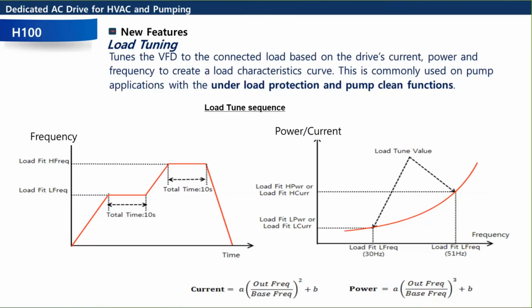So when I say the load, typically this is going to be used on pumps, because if you do a load tune, you're going to be able to do some more advanced features, which we'll mention next, like a pump clean function or under load protection. So like a belt break or broken shaft or pump clean, if something gets jammed up. This diagram on the left is showing the actual load tune. It's going to go up to a certain frequency, run for 10 seconds, get some different data back. Then it's going to jump up to the high frequency, and it's going to do some calculations. It's going to take those frequencies, plug them into this formula, look at the current, and then try to figure out where we are on a pump curve. And it's going to do the same for the power, power and current, and then frequency here.